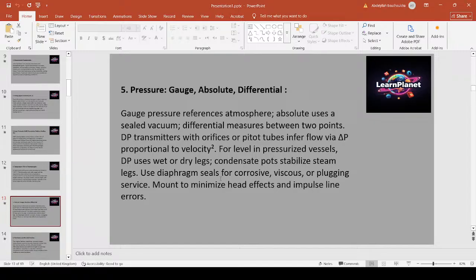Pressure: gauge, absolute, differential. Gauge pressure references atmosphere. Absolute uses a sealed vacuum reference. Differential measures between two points. DP transmitters with orifices or pitot tubes measure flow via delta P proportional to velocity. For level in pressurized vessels, DP uses wet or dry legs, condensate pots stabilize steam legs. Use diaphragm seals for corrosive, viscous, or plugging services. Mount to minimize head effects and impulse line errors.